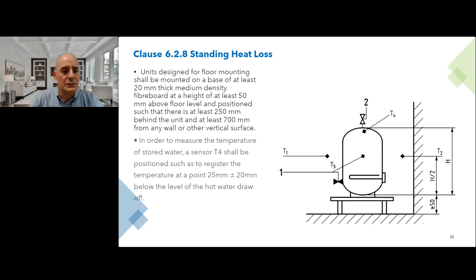In order to measure the temperature of the stored water, a sensor T4 should be positioned such as to register the temperature at a point 25 plus or minus 20 mm. External expansion cylinders, we actually measure the distance specified to the settled level of the water. We would use the thermostat pocket, but otherwise we would ask the manufacturer to put a special stub connection 25 mm below the settled water level, so we can accurately measure the water temperature in the correct position.